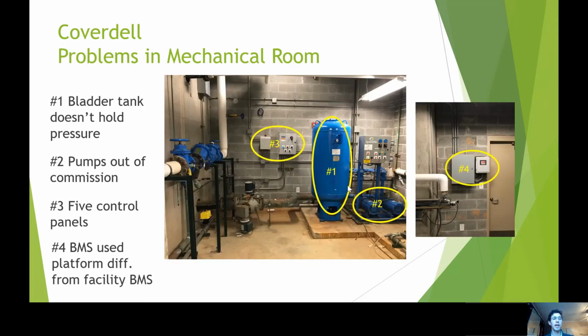So, some other problems in the mechanical room of Coverdell. Currently, the bladder tank doesn't hold pressure. And this is important because it helps prevent frequent pump cycling, which can prolong the life of a pump. And the 2 pumps, as you see in that picture, are out of commission. It's interesting because these 2 pumps are tagged, meaning they are in the maintenance schedule system to be checked on every couple of months by someone from that department. So you can see that it's been checked on for the past 10 years, despite not having worked for at least more than half that time. So just because the pumps are getting checked on doesn't mean they're working.